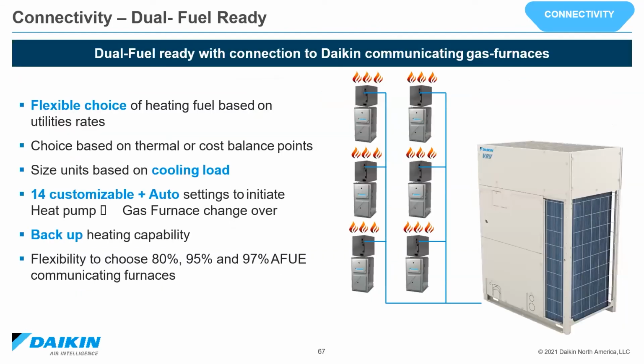For cold climate applications, we have the dual fuel design. The Emerion can be set up to work with Daikin's communicating gas furnaces for an ultra low ambient heating option. So you could utilize the low cost of gas and the efficiency of gas in, say, as far down as -30, -40, all the way up to, say, 0 degrees. And then you utilize the high efficiency of heat pump from 0 up through cooling.